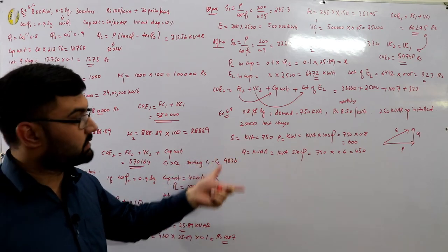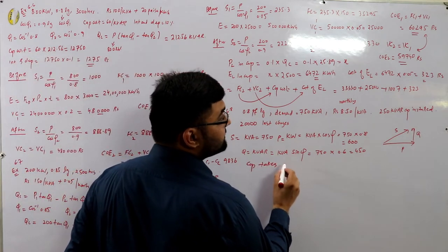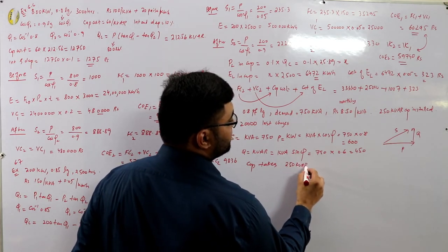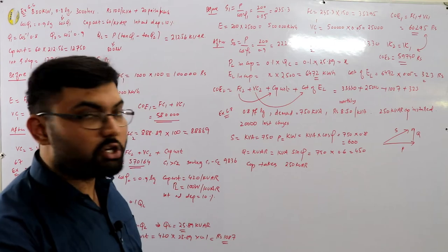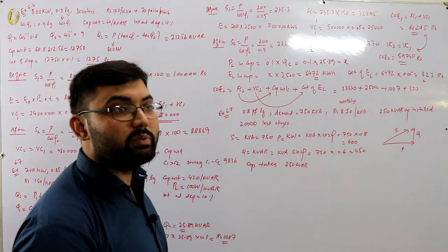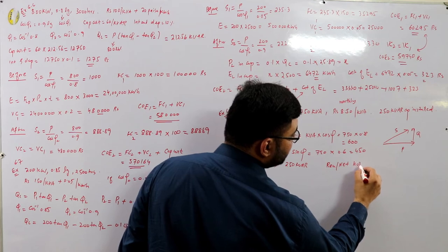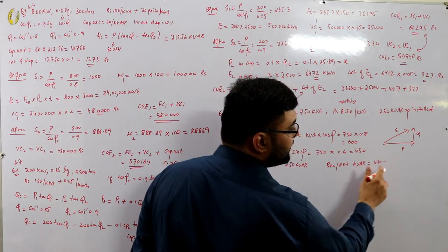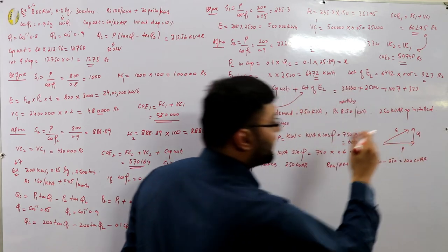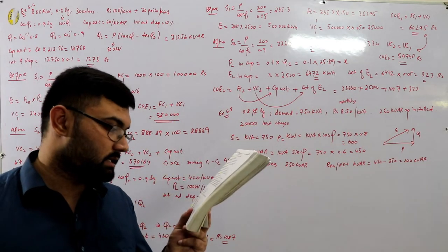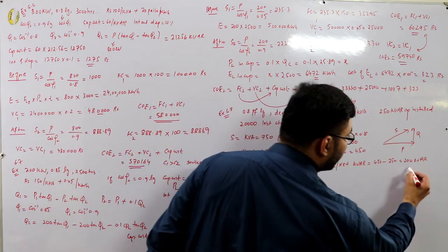Now have a look, these are before power factor correction. Now the capacitor takes 250 kVARs. So if the capacitor takes 250 kVARs, you have injected some leading kVARs of 250. Initially the lagging kVARs are 450. So after the capacitor installation, the net kVARs are 450, which were initial, minus 250 balanced by the capacitor. So you have remaining 200 kVARs after power factor improvement. Isn't it like this? So 200 is the remaining Q.